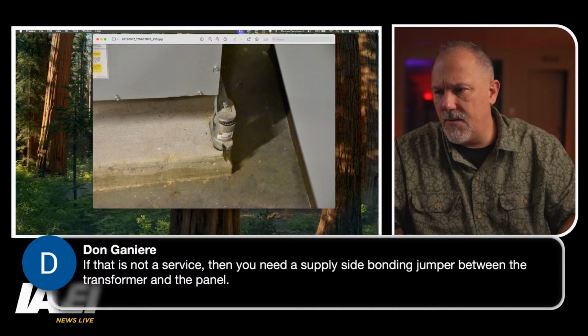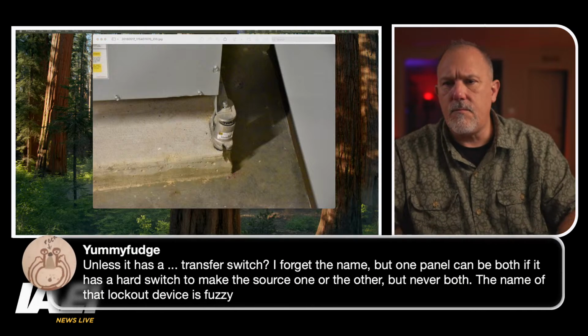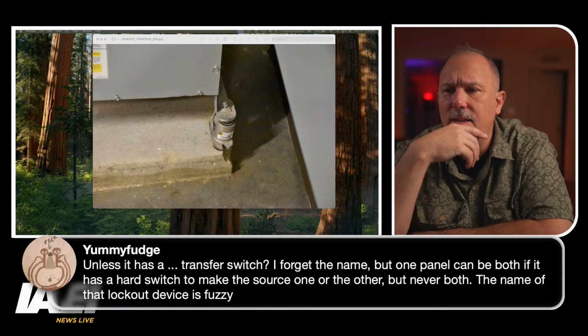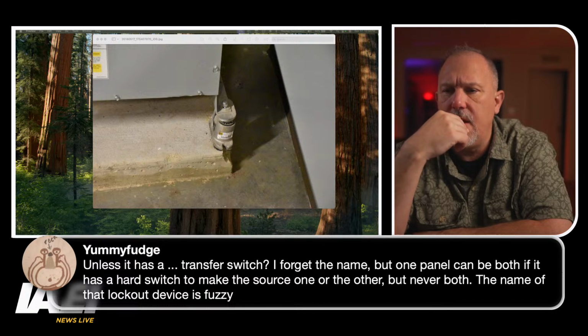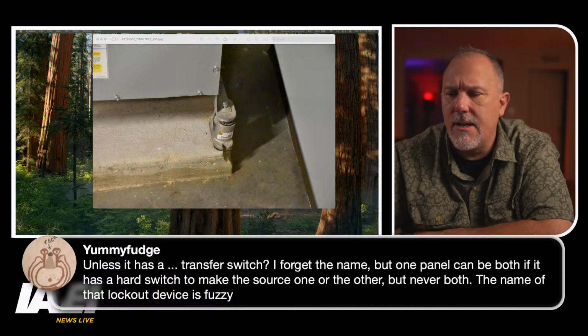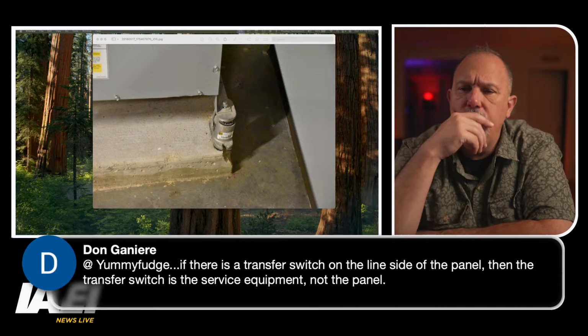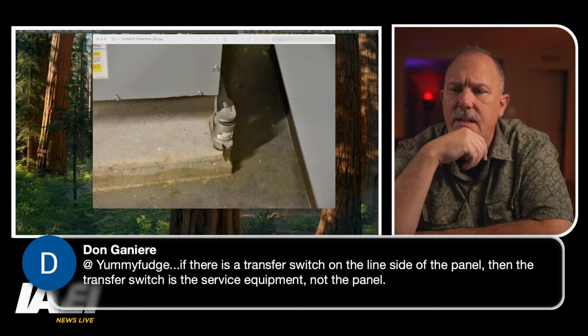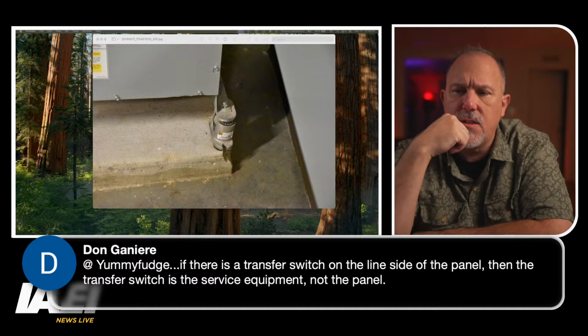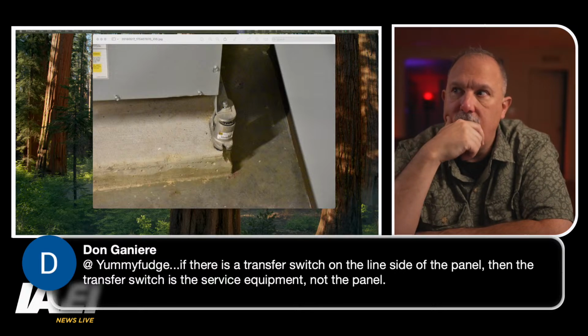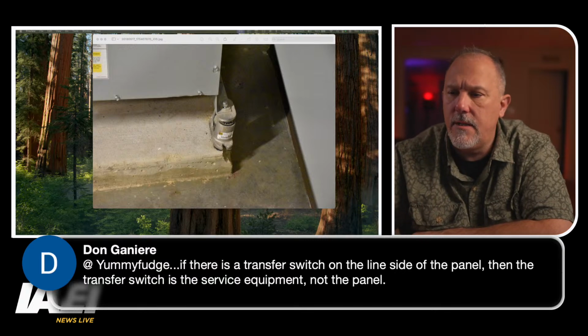If there is a transfer switch, thanks a lot for sharing. Yummy Fudge, unless it has a transfer switch, I forgot the name, but one panel can be both if it has a hard switch to make the source one or the other, but never both. The name of the lockout device is fuzzy. If there's a transfer switch on the line side of the panel, then the transfer switch is the service equipment, not the panel. That's a true statement.